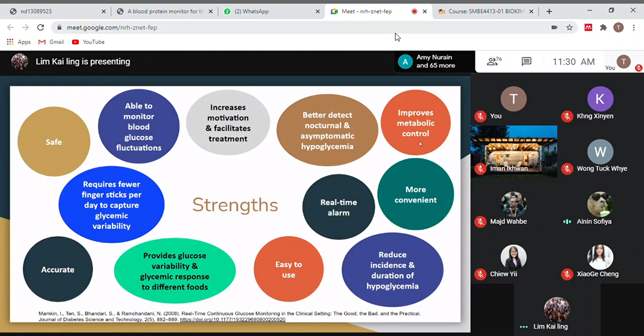The first one is a side effect during usage. Some patients complain that they are not comfortable when they use a sensor, and it causes skin irritation. Besides that, there is some lag time between the real blood glucose and the measurement that the technology provides. That happens when we have a quick change, for example, if the patient eats sweets, or exercises, or something happens with them. This kind of technology cannot detect quick changes directly, so we have a lag time of around 12 to 15 minutes.